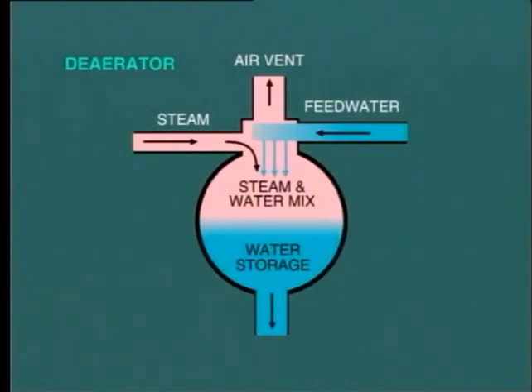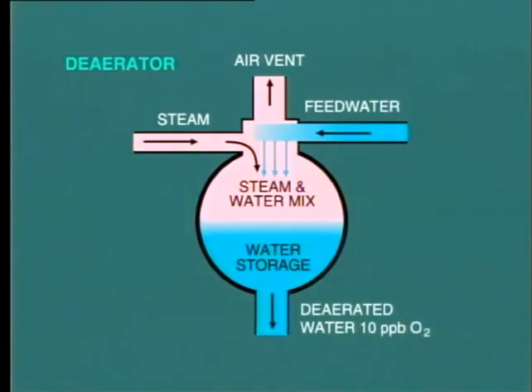The basic function is that the water is heated sufficiently to liberate and expel any gases from the solution. Modern de-aerators can reduce the dissolved oxygen content in feed water to about 10 parts per billion and even lower.